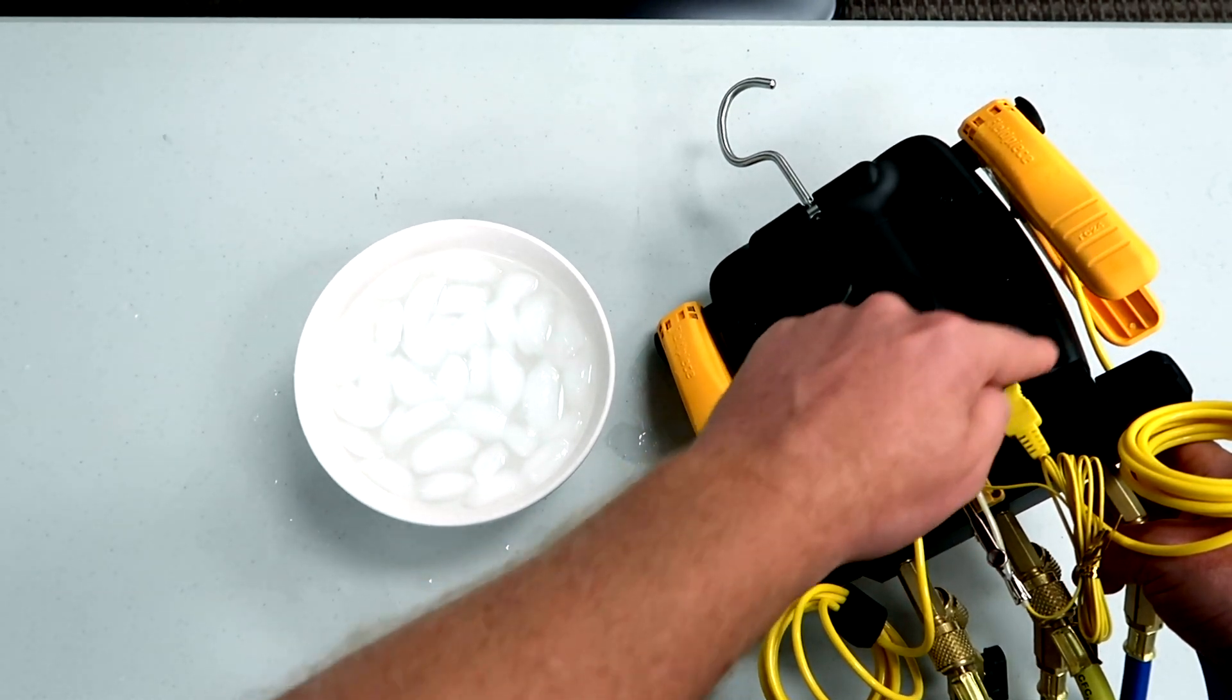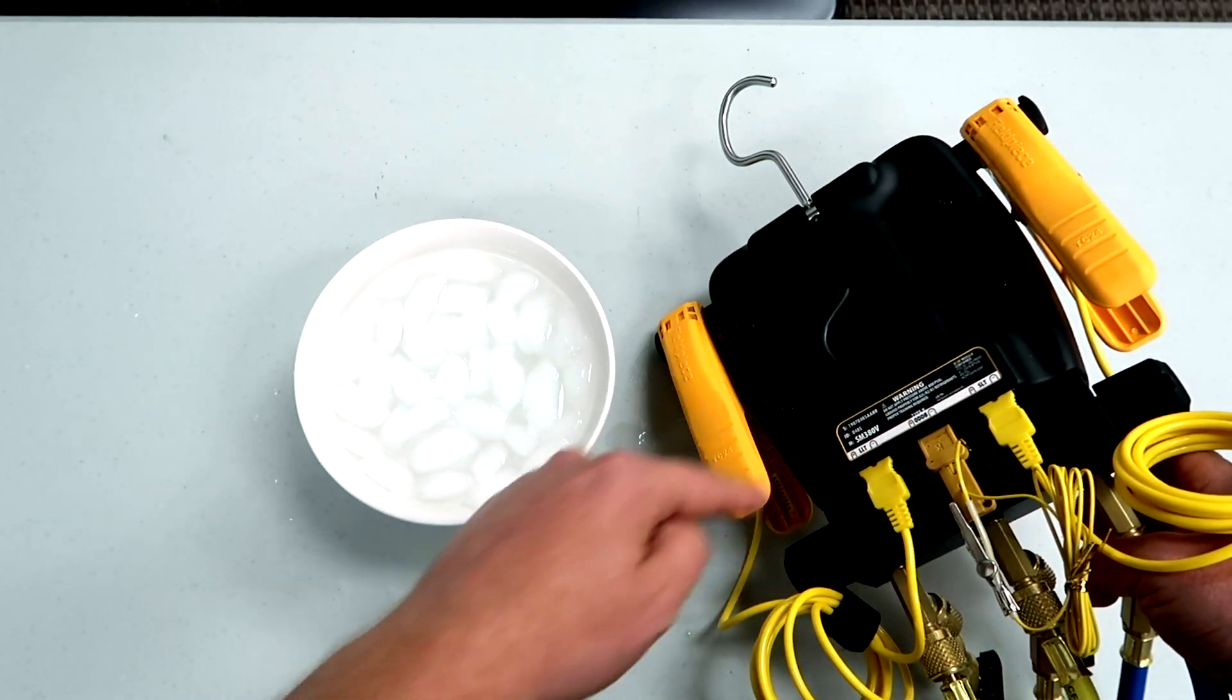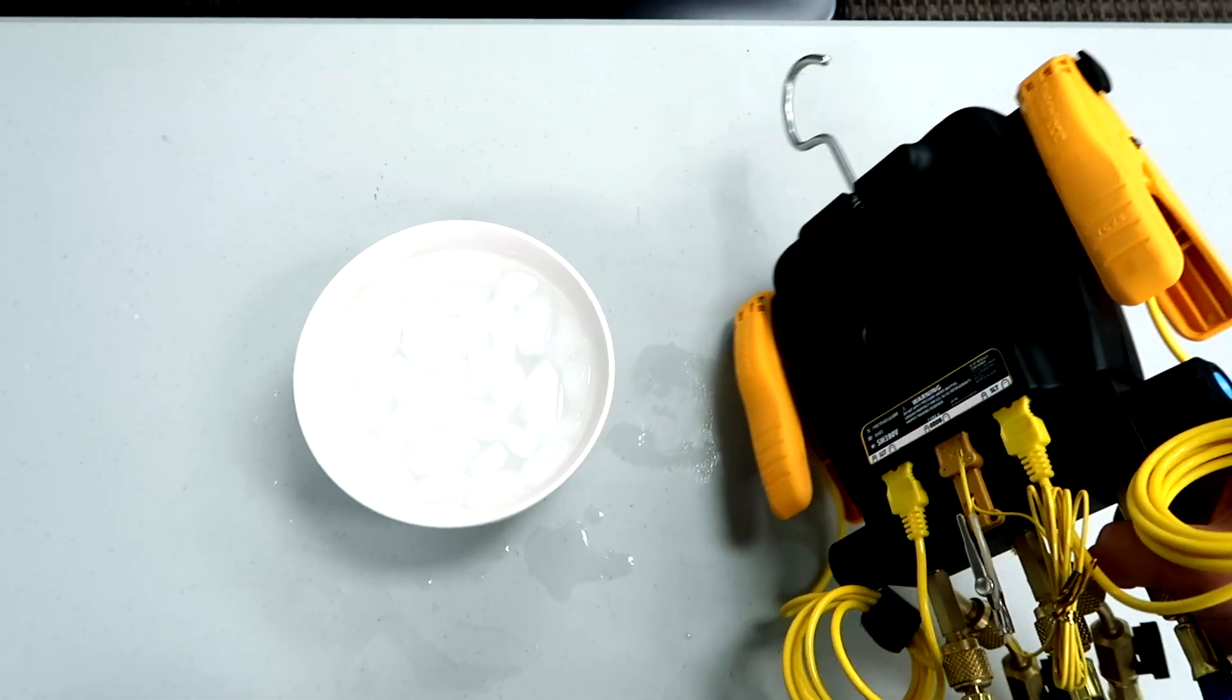The calibration has to stay with the same port. We couldn't calibrate and then move this thermocouple over to the other side. We have to keep them on the same ports or we have to recalibrate.